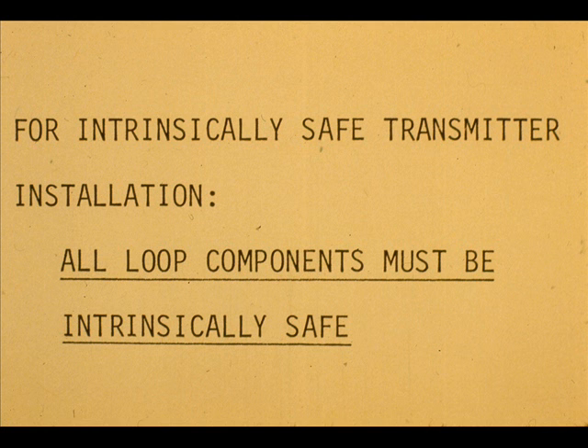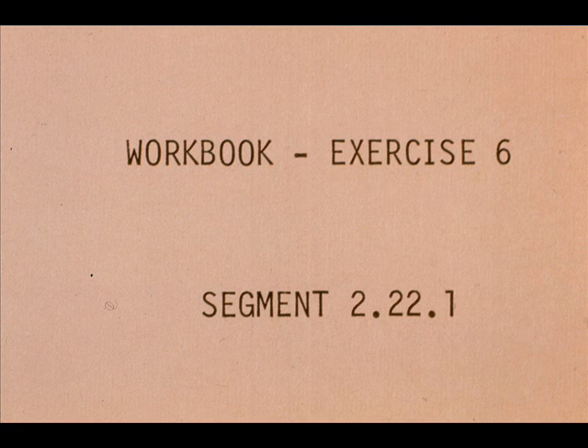Veritrac transmitters are suitable for use in hazardous areas such as National Electrical Code Class 1, Group C or D, Division 1 areas. However, for any transmitter to be intrinsically safe, all items in the loop must also be intrinsically safe. Now work exercise number 6 in your workbook.